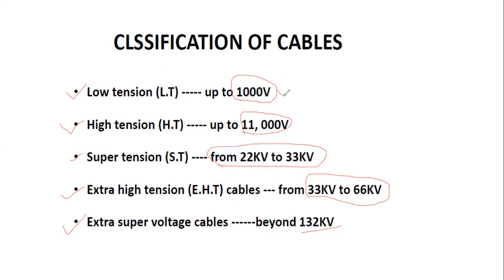To summarize the classification by voltage levels: low tension cables are used up to 1000 volts, high tension cables up to 11,000 volts, super tension cables 22 to 33 kilovolts, extra high tension cables 33 to 66 kilovolts, and extra super voltage cables beyond 132 kilovolts.